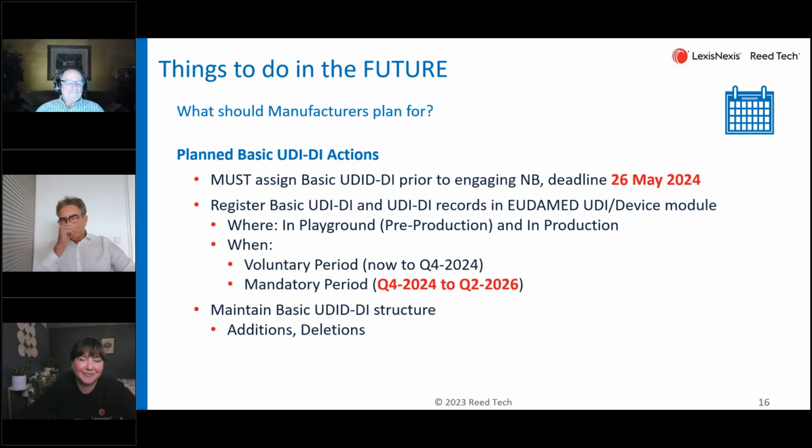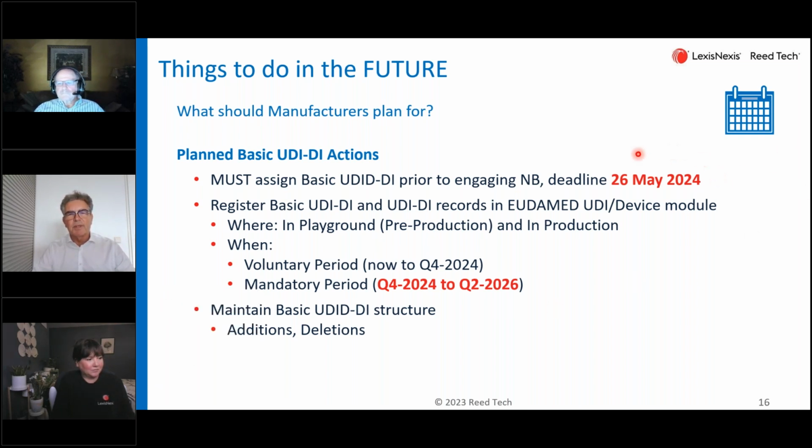Yes, we have now this regulation 2023/607, which is called the extension regulation, but the extension is not for manufacturers, only for notified bodies. They have more time to take care of their certification work. Manufacturers must comply by 26 May 2024. That's less than 8 months from now. Really, that's just over, what is it, 32 weeks. That's basically tomorrow. So then you need to be ready.